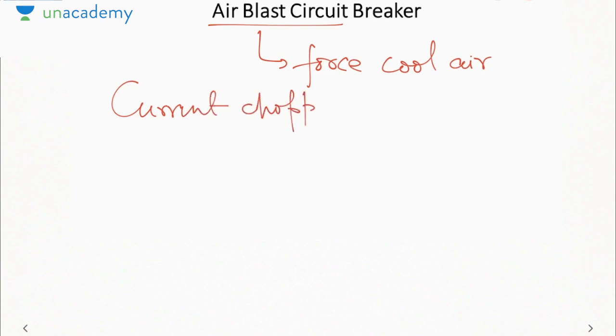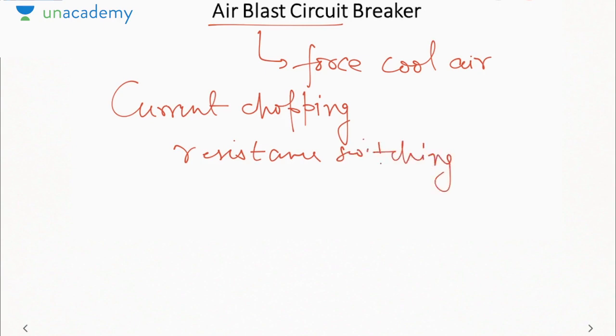So remember, current chopping is most severe in the air blast circuit breaker, due to which we have to use resistance switching. Resistance switching needs to be used for avoiding the current chopping phenomenon in the circuit breaker. Usually these circuit breakers are used at high voltages, that is EHV and UHV applications, that is extra high voltage and ultra high voltage.